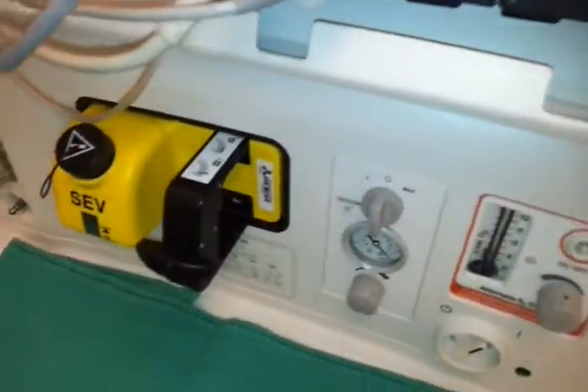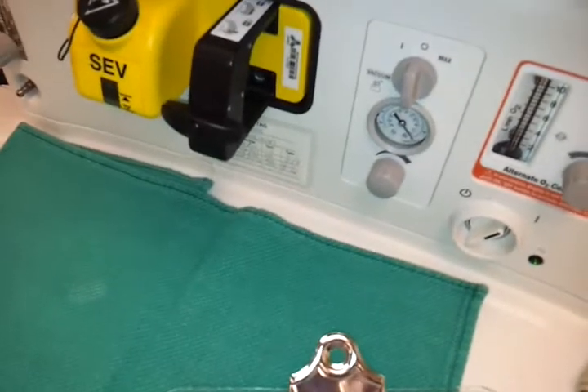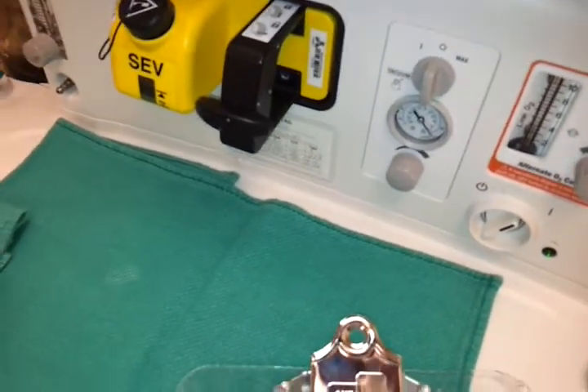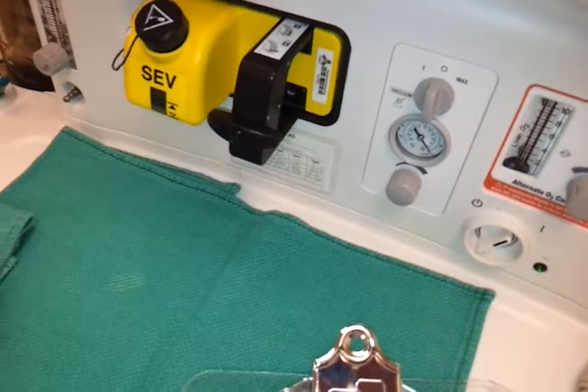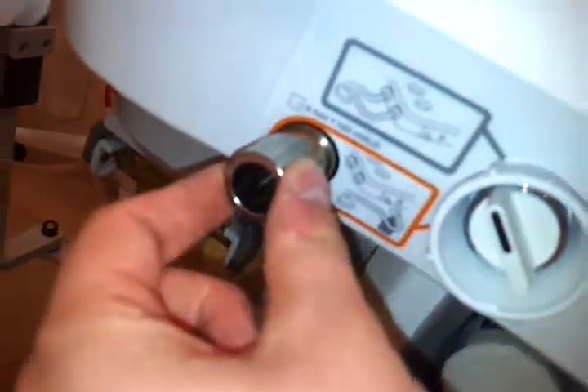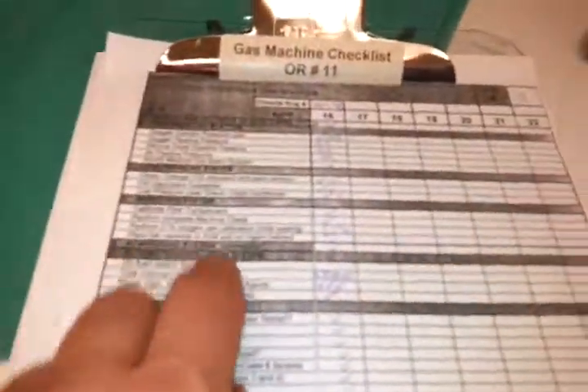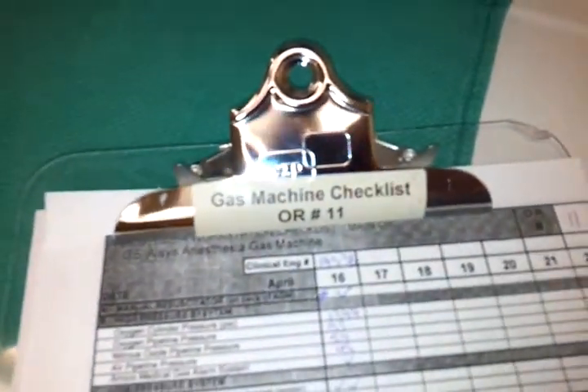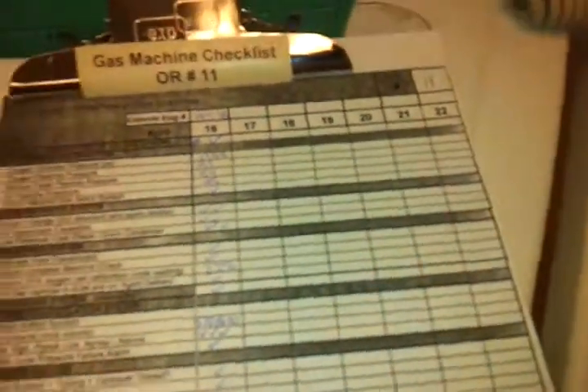While that's going on, we can look at the checklist. The second part's the low pressure system. So check the CO2 absorbent, which we did, fill the vaporizers, and the low pressure check, which was the one we did right here with the bulb. So that's done. The scavenging system, you just have to make sure it's connected. That's that pink line in the back, which we already checked. Automatic ventilation system, so that's the last part you do. Basically turn the vent on. There's the monitor vacuum. That's all your equipment, which Cody's going to go over in just a second.